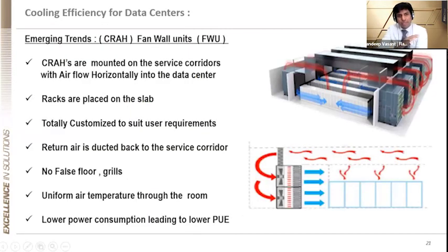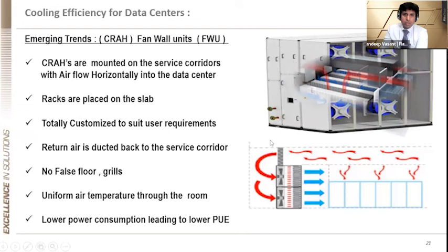From indirect and direct free cooling, I shift gears towards the emerging trends in a large hyperscale data center. So let's take an example of a large hyperscale data center. Instead of placing, let us say, multiple 30 or 40 TR units and having multiple chillers and multiple indoor units, we also look at the trend of placement of fan wall units. What are fan wall units? These are large, customized air handling units placed directly on the slab. So we eliminate the false floor, completely customized to meet larger capacity and larger airflow CFM. The cold air is given, and we do a hot-air containment back to the unit. Obviously, these units would be connected to the chiller, which can be single or multiple chillers, dual coil, maybe chiller A operates, and then when chiller A is shut down, chiller B comes into picture. So as I said, these are the fan wall units.